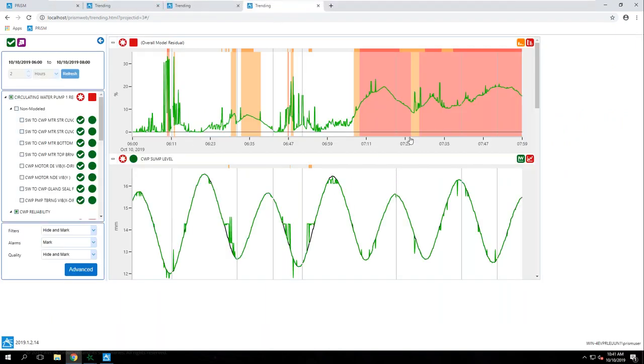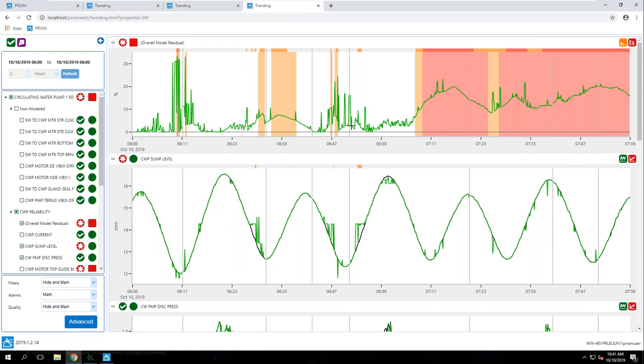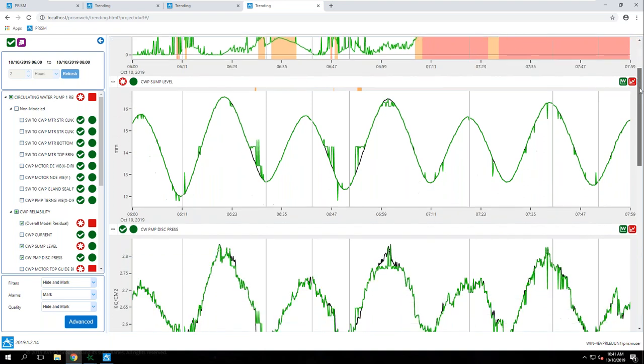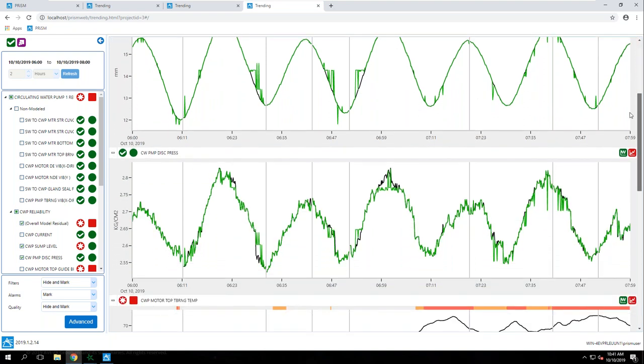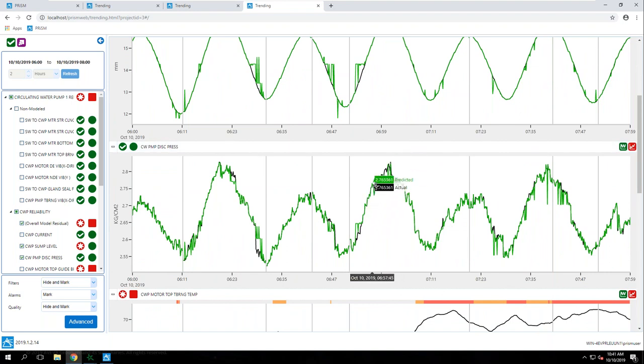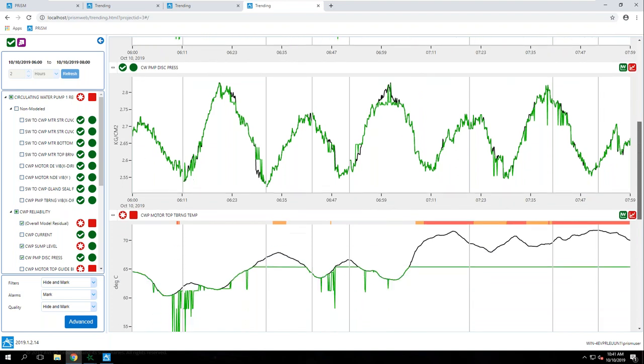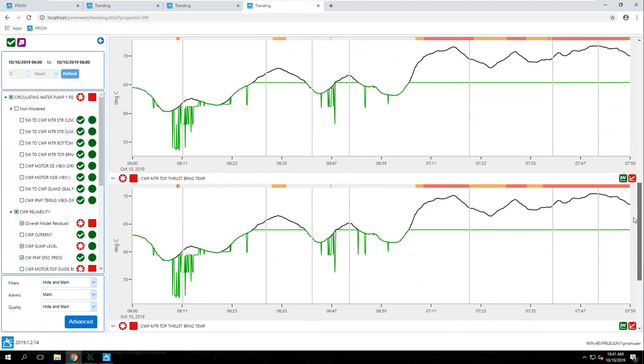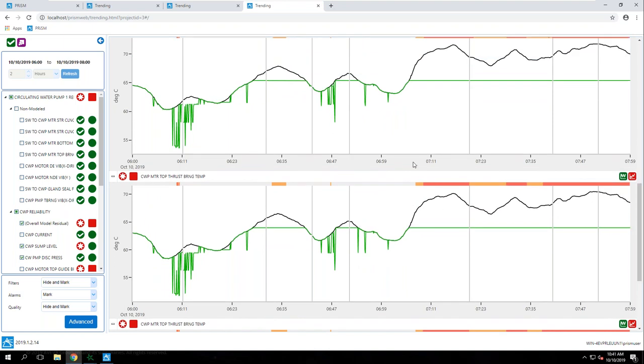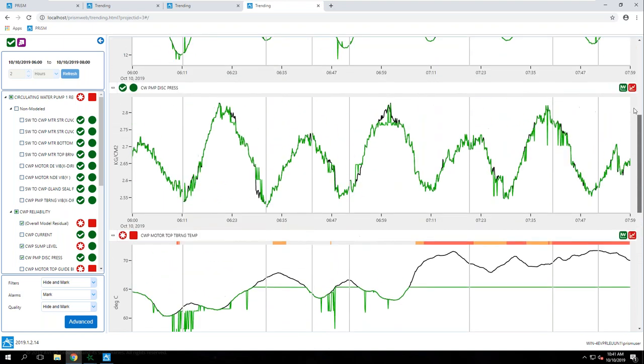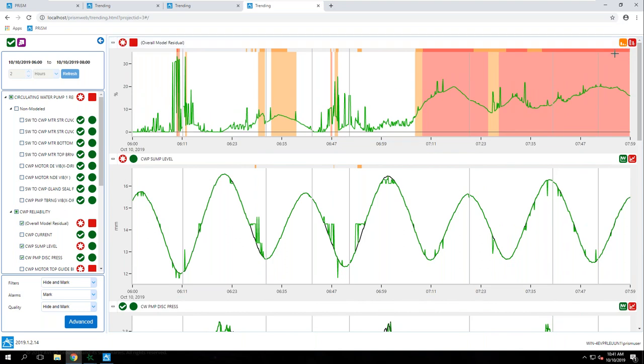Now I've already zoomed in on a trend earlier. The top trend will always show our overall model residual, that drift of the model as a whole away from the predicted state. Beneath that, we have all of the individual signals plotted, showing their actual values in black, as well as the predicted state in green. You can see some of our tags or signals have drifted much further away than others, giving some idea of leading indicators, which individual tags or instrumentation are the biggest contributors to the model deviation.